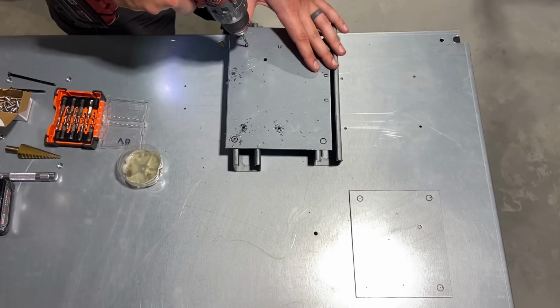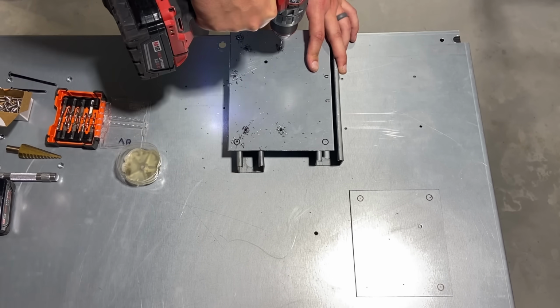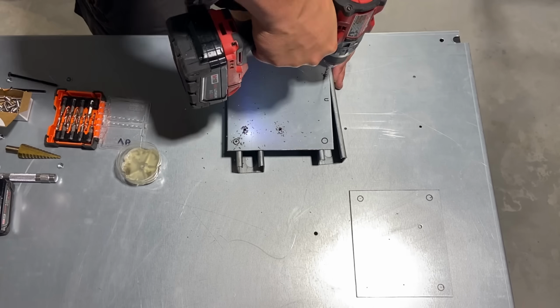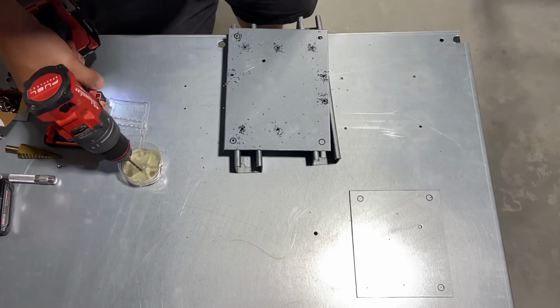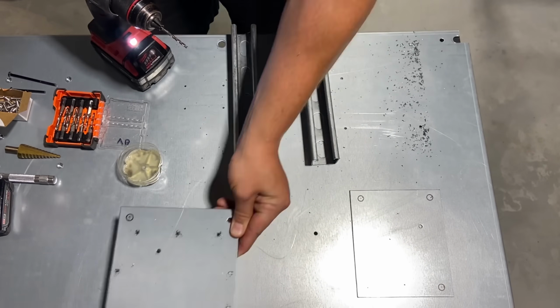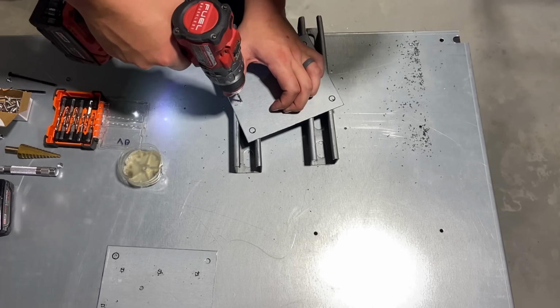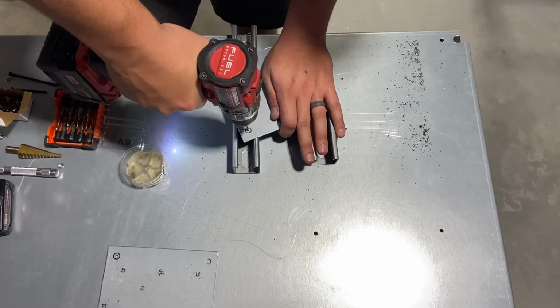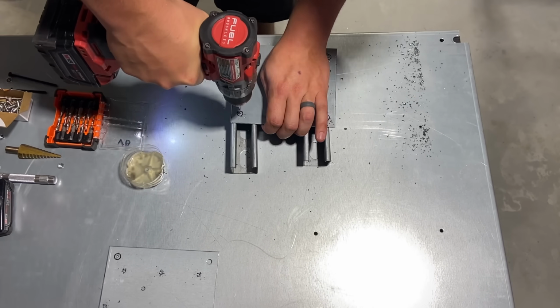Speaking of that circuit breaker, I didn't even say what it was for. That will be the circuit breaker for the generator, for the incoming power from the generator, so if I need to shut it off, I can do so without going all the way outside and turning the generator off. It's just a local disconnect and local overcurrent protection for that power source.